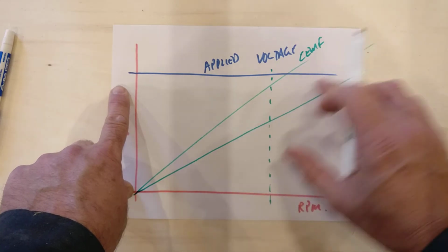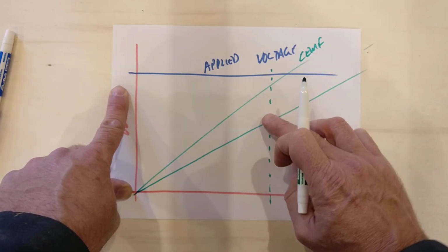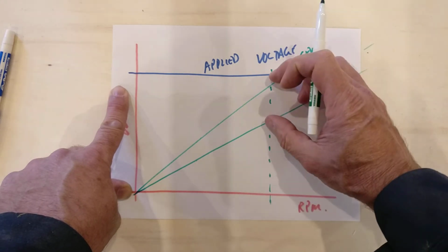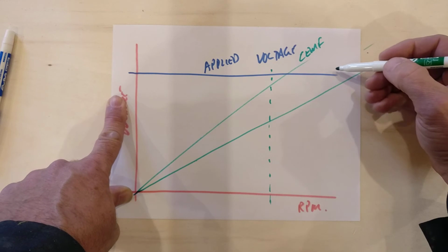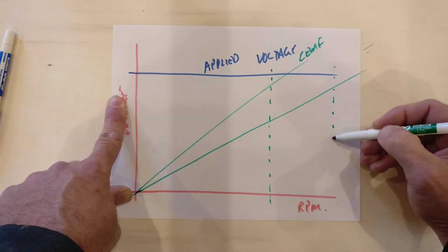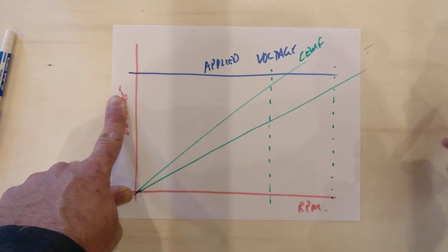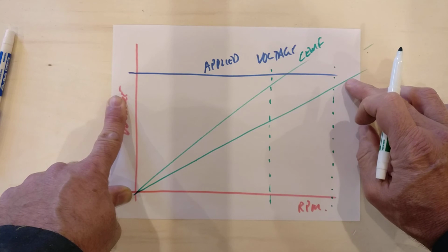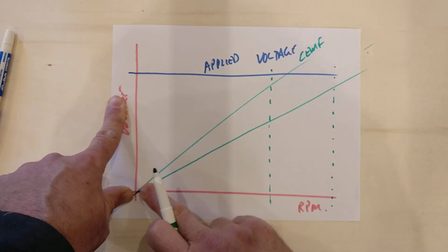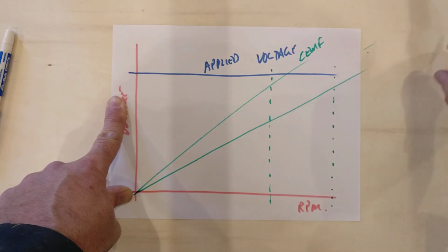And now, if I've reduced the strength of the field, the motor current would certainly start to increase because the net armature voltage has increased. It would start to spin up and it would start to try to run again where the counter EMF is close to the applied voltage. So now here's my new RPM that it's running with a weakened field. If I continue to weaken the field, it becomes even harder to produce counter EMF and it'll want to start to run way up here somewhere.